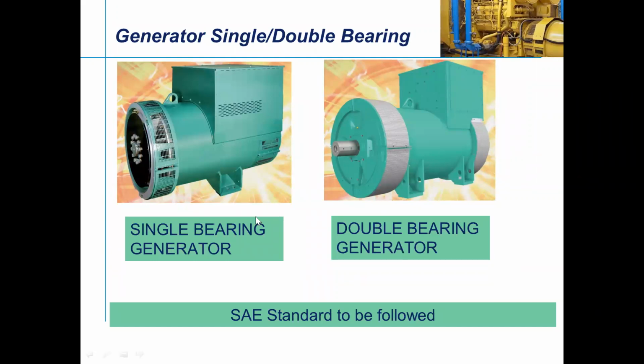On the left-hand side of the generator, you can see the single bearing. What we mean by single bearing is that the disc is directly coupled to the engine flywheel, that is, to the prime mover. In case of a double bearing, there are two bearings, one on the DE side and one on the NDE side. Conventionally, for turbines and other applications like shaft generators and marine, they go for a double bearing, where the torsional load sharing will be better. But single bearing is also used, presently up to 2.5 megawatts.